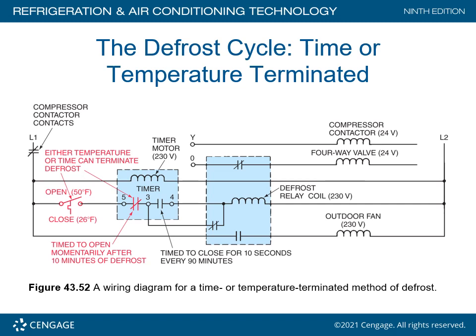No problem. And remember, this electronic timer board is designed to close for 10 seconds every 90 minutes. This board runs 24/7, whether it's in heating or cooling. But if it's in a heating mode, it'll read every 90 minutes in this particular situation. The contacts will close for a period of 10 seconds. And so if the other switches are not made, we don't go into defrost. It's as simple as that.